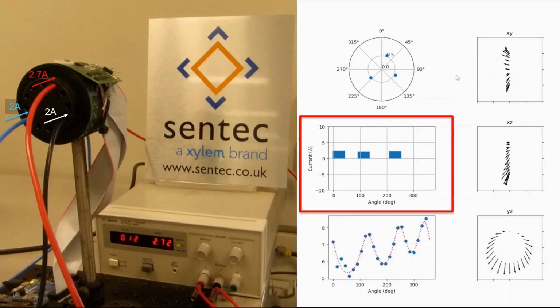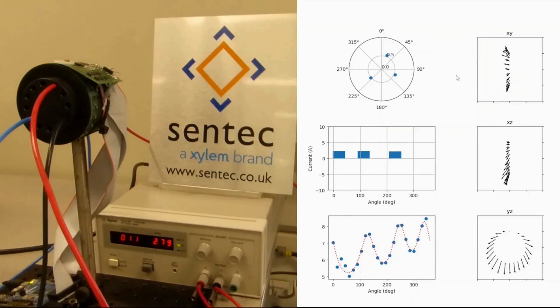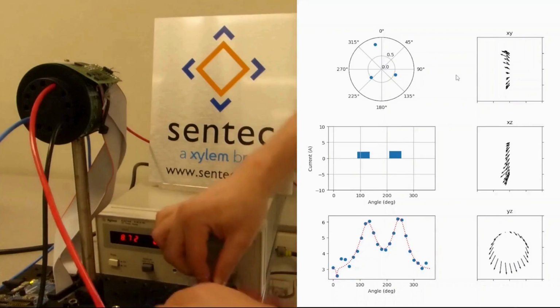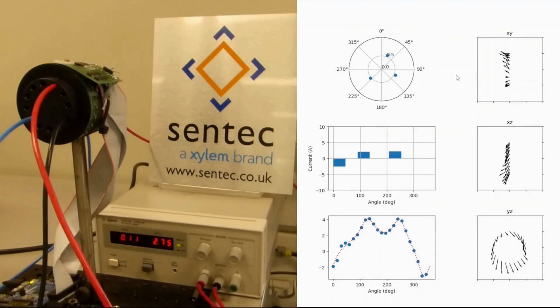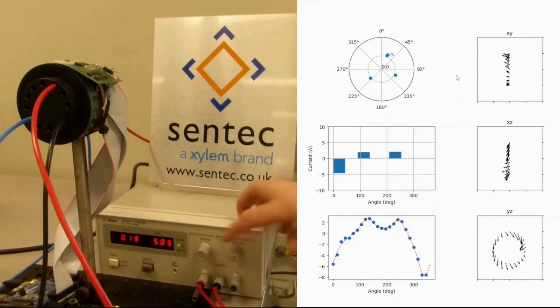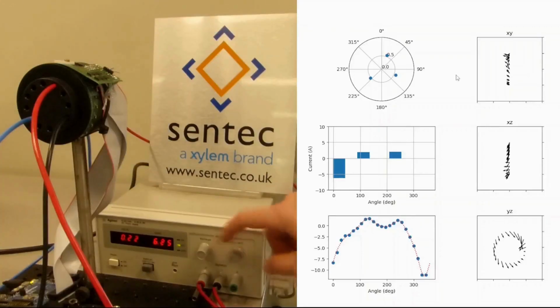This plot shows the measured magnitude of the current through the conductors against the angular position. The current in the red wire can be seen at the 20-degree position, which is currently equal to 2.7 amps. Here we see the Multi I Probe measuring DC current in all three conductors. Changing the polarity of the red wire results in a corresponding change in the measured current. Similarly, by increasing the current in the red conductor, we see a corresponding increase.